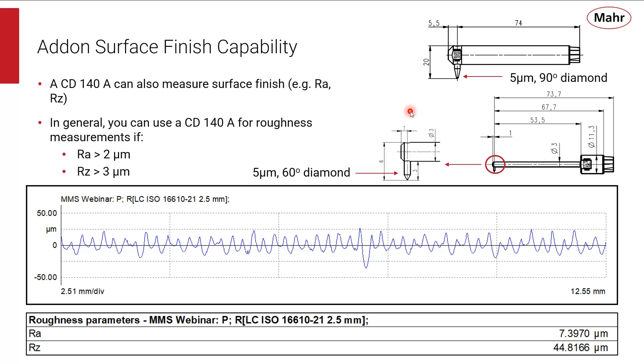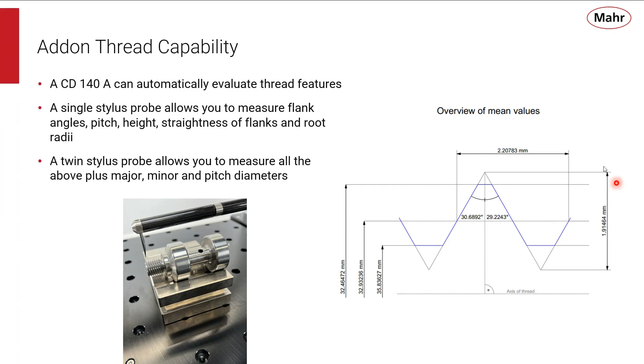And lastly, you can also perform automatic evaluation of threads with add-on thread software. So once you measure a thread with a single stylus, you can measure flank angles, pitches, height, straightness of flanks, and root radii. And with a twin stylus like you saw before, you can measure all of those things plus all of your diameters, your major, minor, and pitch diameters. So we'll automatically evaluate all of those things on your thread and give you an output of each individual measurement, plus an overview of the average values within that thread.